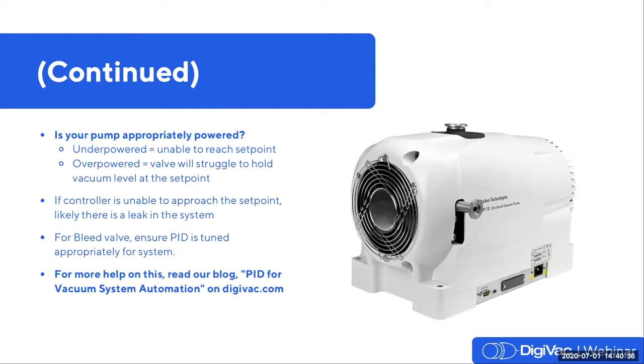For a bleed valve malfunction, always ensure that the PID settings are tuned appropriately for the system. We have conveniently hosted a blog on this subject called PID for Vacuum System Automation at digivac.com, which can be referenced at any time.